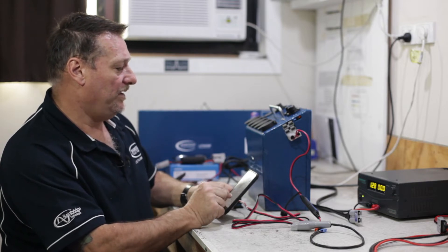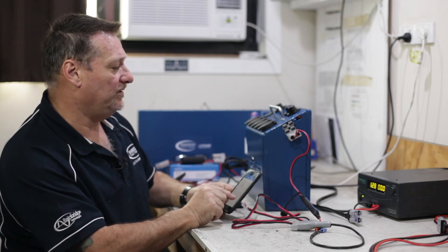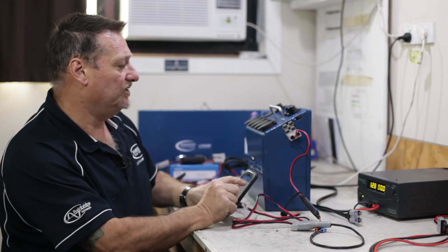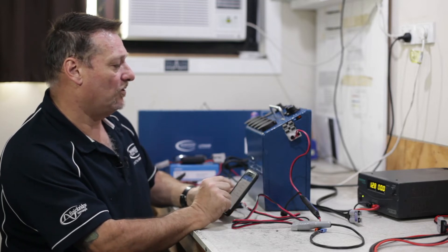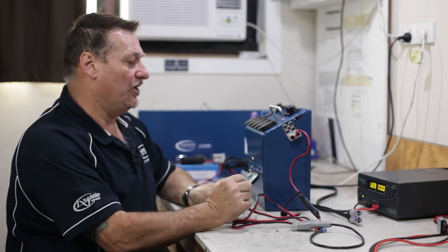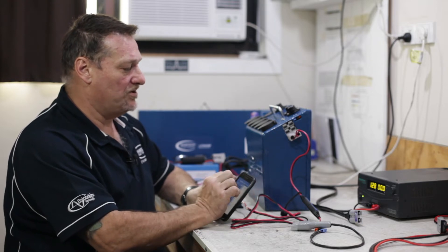It is now charging in the bulk mode. On your Bluetooth device it's telling me the battery voltage is at 14.2 volts and it's charging at 4.5, 4.4, 4.1 amps. Because this battery is pretty much fully charged you'll notice this will just gradually go down very quickly.